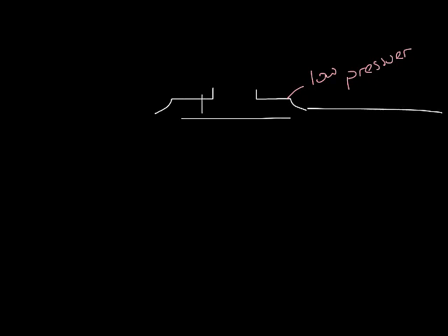So if you remember back in the throw podcast, when the air leaves the diffuser, a low pressure zone is created that causes the diffuser to be pulled towards the ceiling. Remember, this is the Coanda effect. So let's start with the diffuser in the room. The air pattern will travel along the ceiling until the velocity slows to about 75 feet per minute.